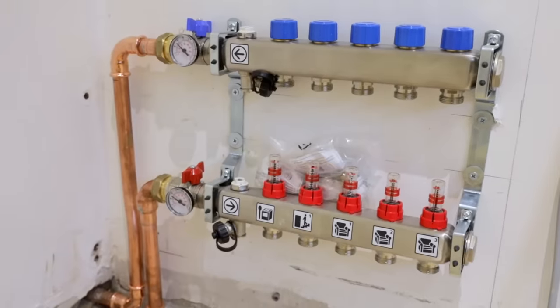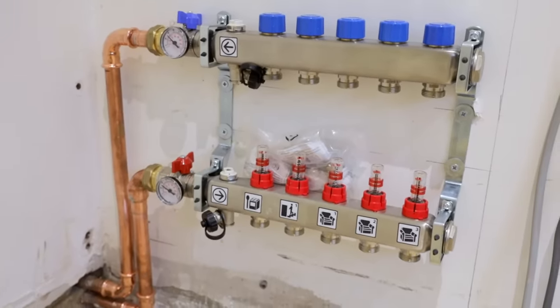In the kitchen we'll have a new manifold. This manifold doesn't have any actuators, pump groups, or blending valves because we don't need them. We'll run the whole system — underfloor heating and radiators — at the same flow temperature of 45°C, because we've designed the system to give the correct output in every room on every floor.